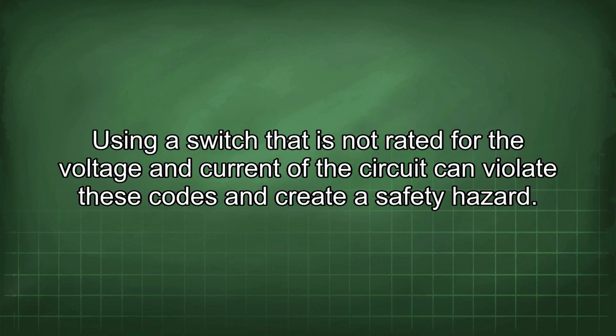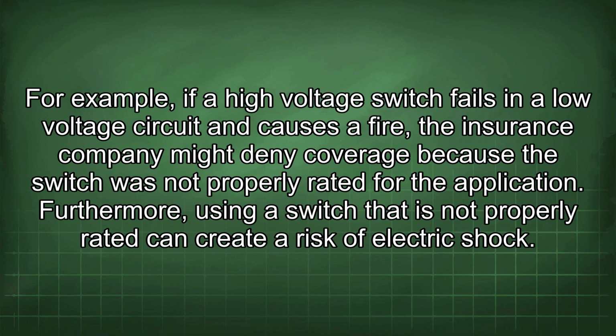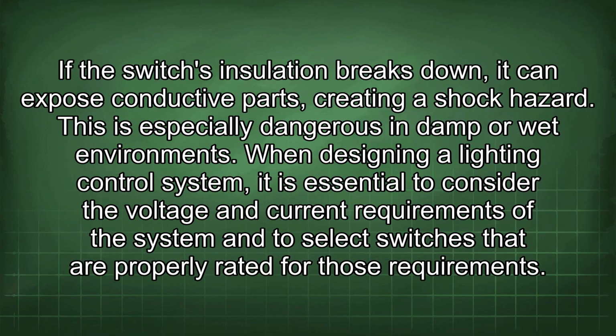Using a switch that is not rated for the voltage and current of the circuit can violate these codes and create a safety hazard. For example, if a high voltage switch fails in a low voltage circuit and causes a fire, the insurance company might deny coverage because the switch was not properly rated for the application. Furthermore, using a switch that is not properly rated can create a risk of electric shock. If the switch's insulation breaks down, it can expose conductive parts, creating a shock hazard. This is especially dangerous in damp or wet environments.